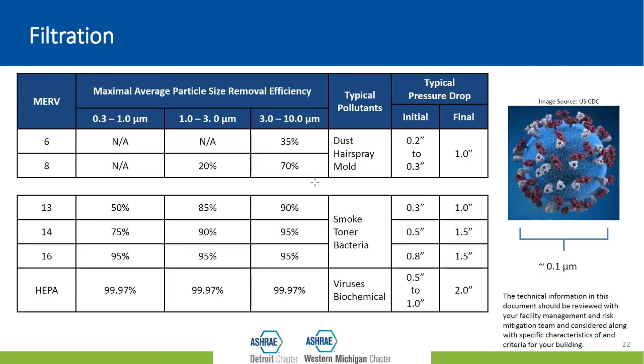Now, some people are very interested in moving from whatever they have to a HEPA filter, because the size of this coronavirus, which is similar to other viruses, is just 0.1 micrometer, right? So that's smaller than what typical filters are being rated for anyway. Just because they're not rated for that doesn't mean that they can't remove particles of that size, but that's just not how they're rated, right?